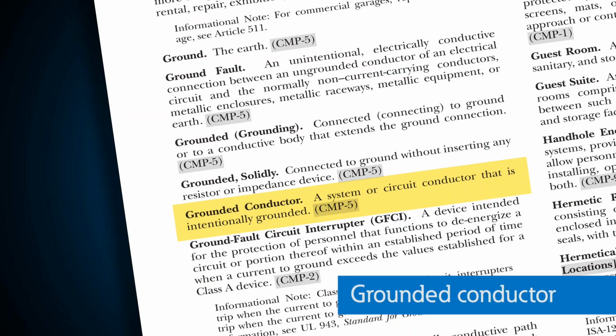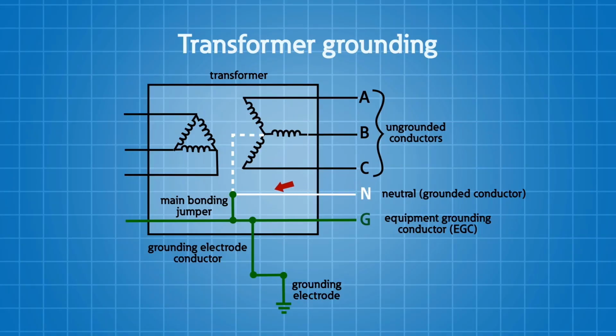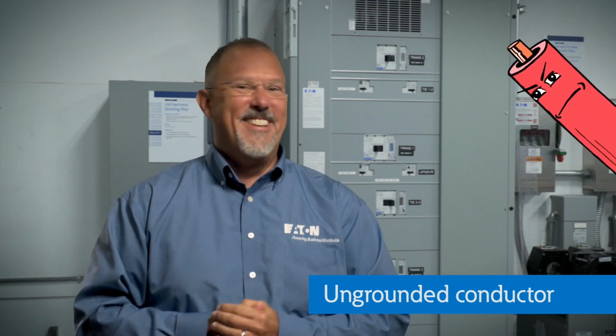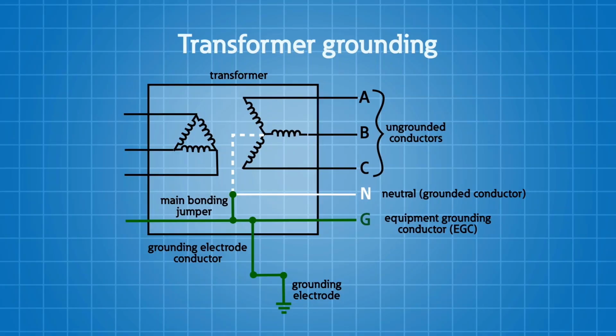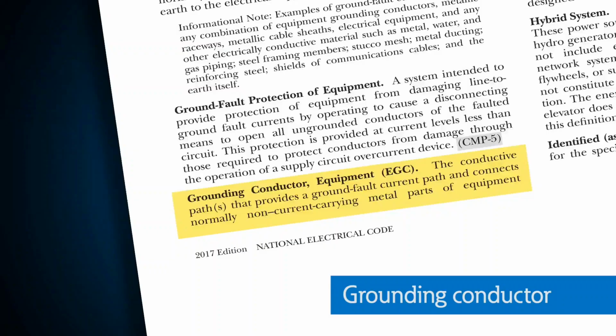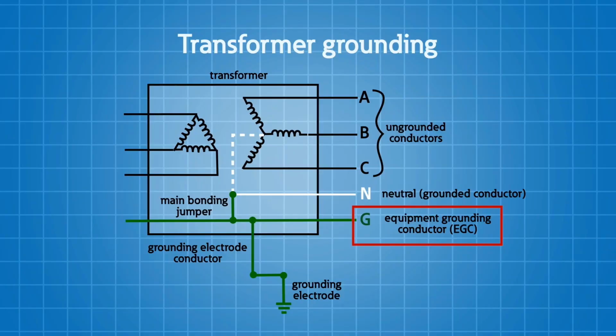All right, so now we're going to talk about the grounded conductor. This is the system or circuit conductor that is intentionally connected to the earth at that one point. We usually refer to this as the neutral. And its ugly brother, the ungrounded conductor, is a circuit conductor that is not intentionally connected to the earth. So this is usually your phase conductors. I know we're saying a lot of terms here with grounded conductor, ungrounded conductor. Now we're going to talk about the grounding conductor. That's a conductor that is used to connect the equipment or the grounded circuit of a wiring system to a grounding electrode or to the grounding electrode system.